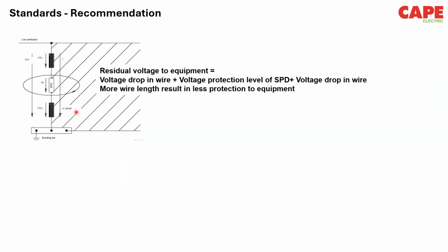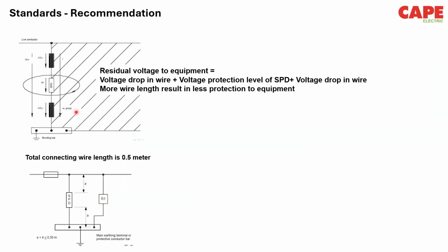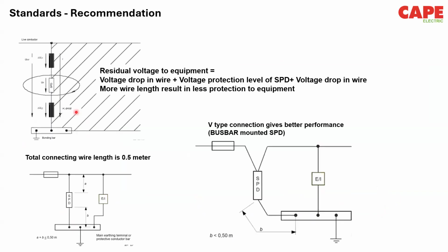What do standards recommend? Standard recommends this 50%, 0.5 meter requirement, or you do a V-type connection. A V-type or a bus bar mounted connection. So basically the SPD will directly be connected to the panel, the bus bar, or you have a line which will come to the SPD and there's generally a second port through which you can directly connect to the line again. So we call it a V-type connection.